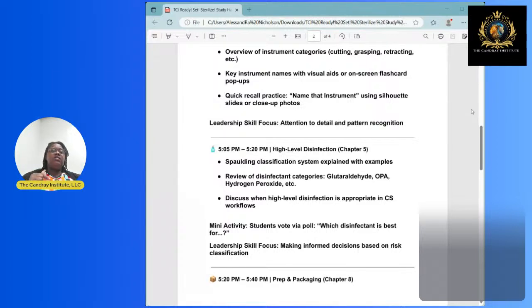Spaulding classification system lets you know what level of instrumentation you're dealing with based on how that instrumentation is introduced to the body. Non-critical instruments are introduced to intact skin. A stethoscope goes on the outside and checks you. No cuts. It ain't going in nothing. Non-critical. All that needs is to be low-level or intermediate-level disinfected. That's going to be a cavi wipe or wipe down. Semi-critical devices are going to be the ones that come in contact with the mucous membranes. Anything going down your throat or going up your anus. I hate to be that person, but we're talking about surgery. Okay, so we'll talk about surgery.